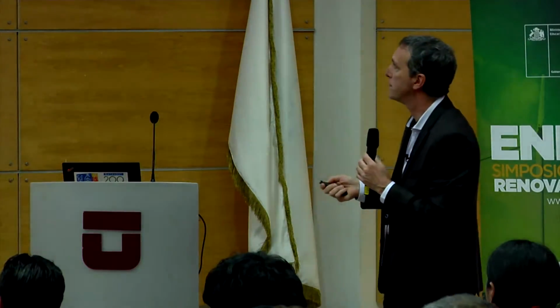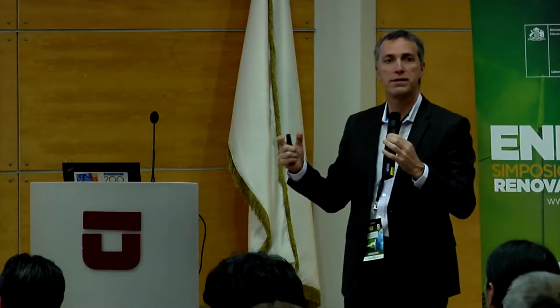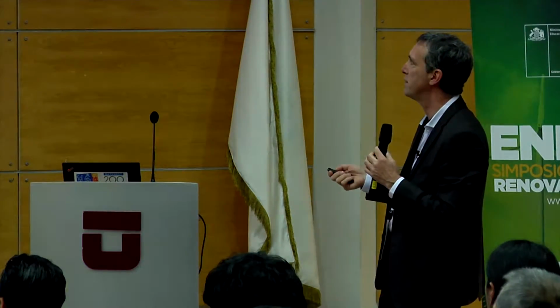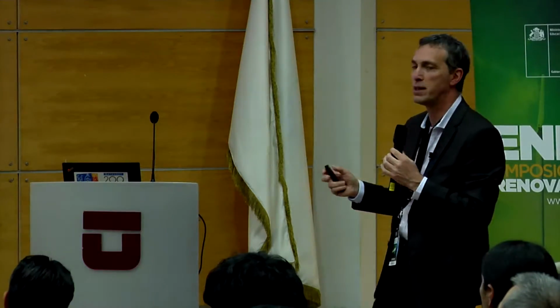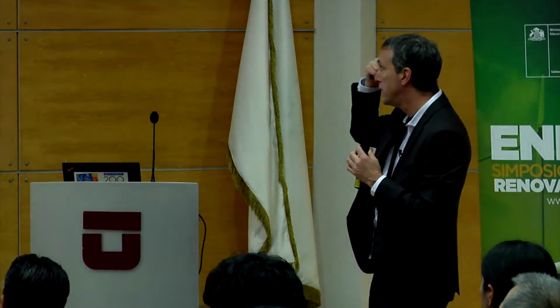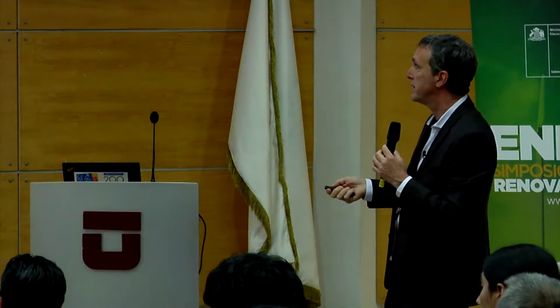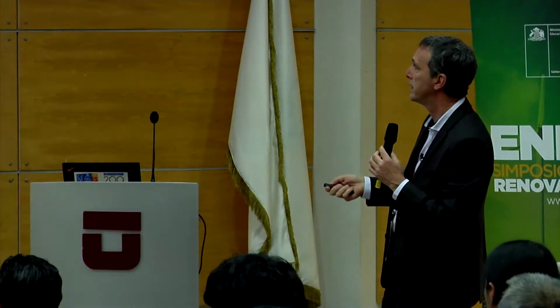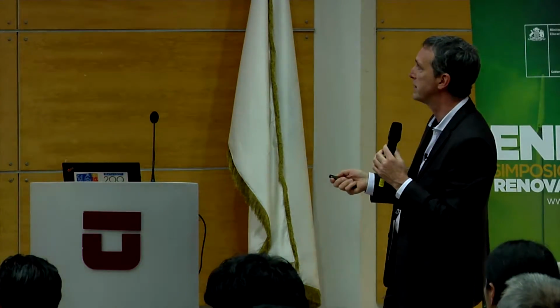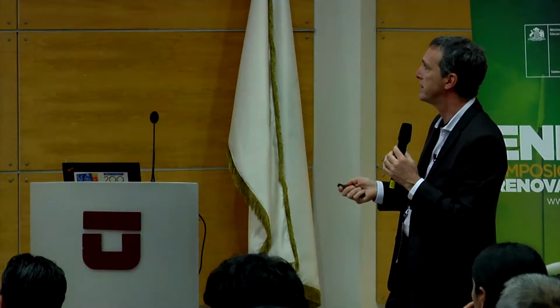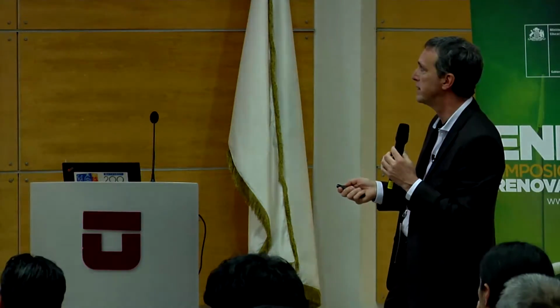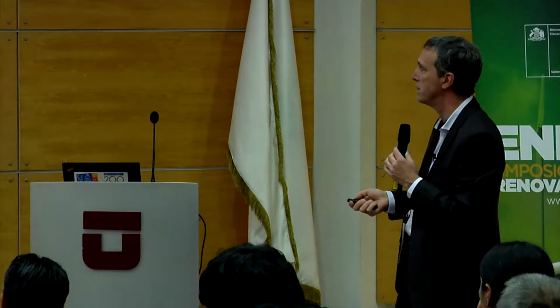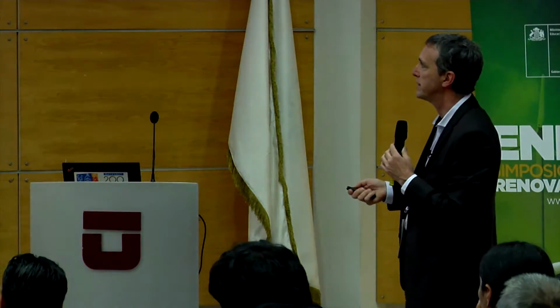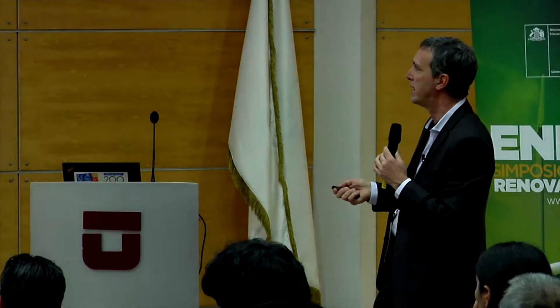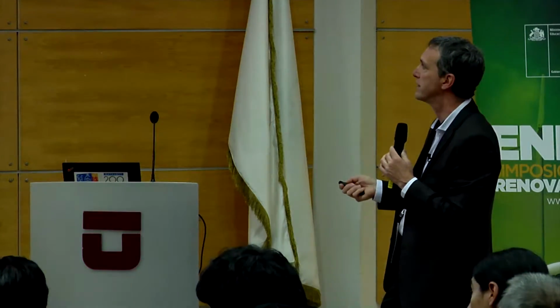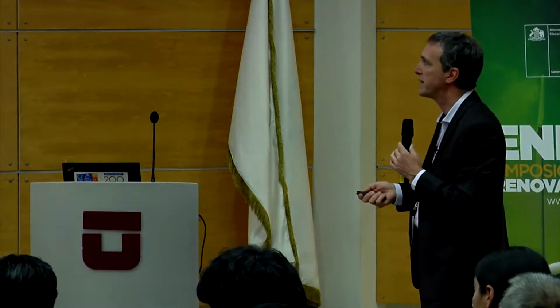Each UNIFLEX module is one of those building blocks, rated about 25 kilowatt with a DC link voltage of approximately 1.1 kilovolt. The two H bridges and the DC link are connected to each side of the transformer. We're talking about a 3.3 millifarad DC link capacitor at 1,350 volt.